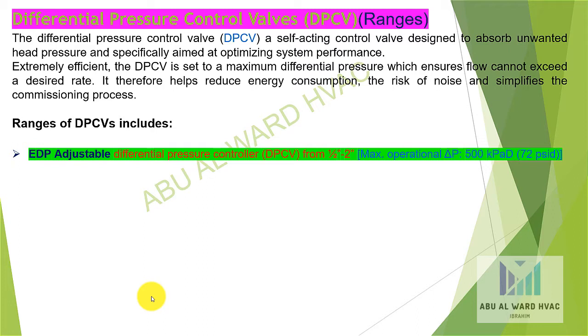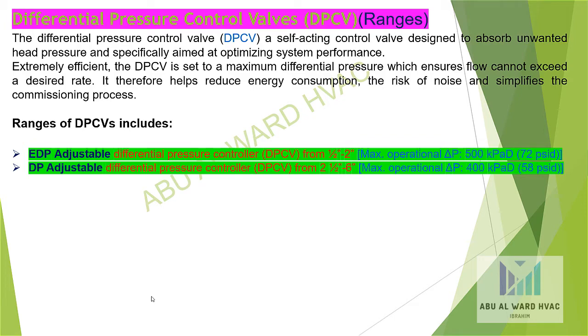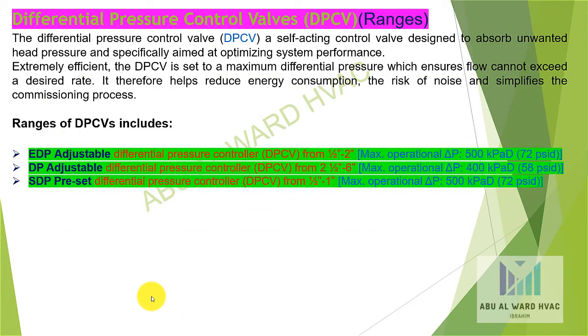The DPCV is set to a maximum differential pressure which ensures flow cannot exceed a desired rate. It therefore helps reduce energy consumption, the risk of noise, and simplifies the commissioning process. Ranges of DPCVs include: EDP — adjustable differential pressure controller, half to two inch, maximum operational Delta P of 500 kPa (72 PSI). DP — adjustable differential pressure controller, two and a half to six inch, maximum operational Delta P of 400 kPa (58 PSI). SDP — preset differential pressure controller, half to one inch, maximum operational Delta P of 500 kPa (72 PSI).